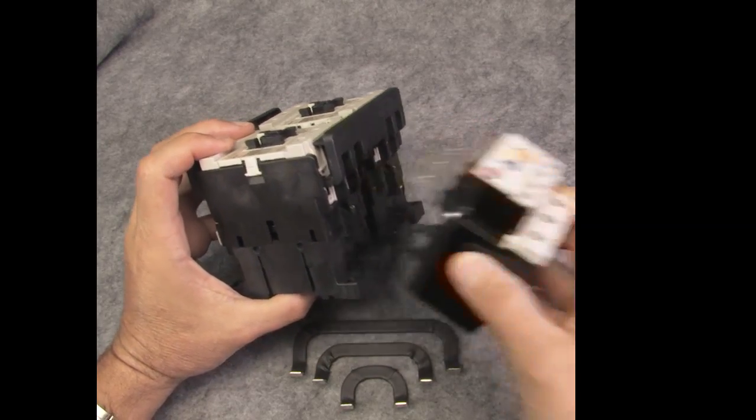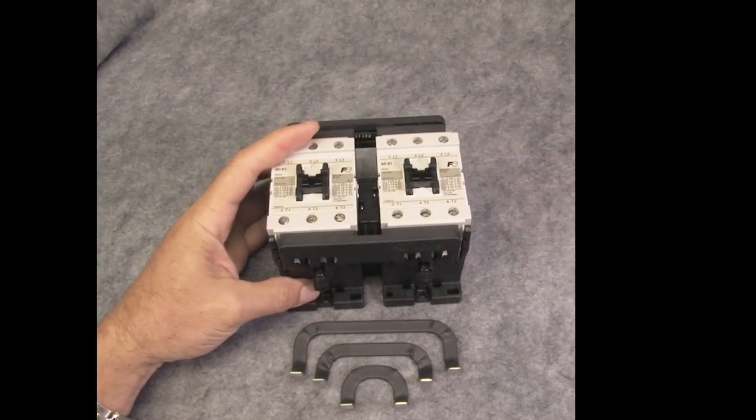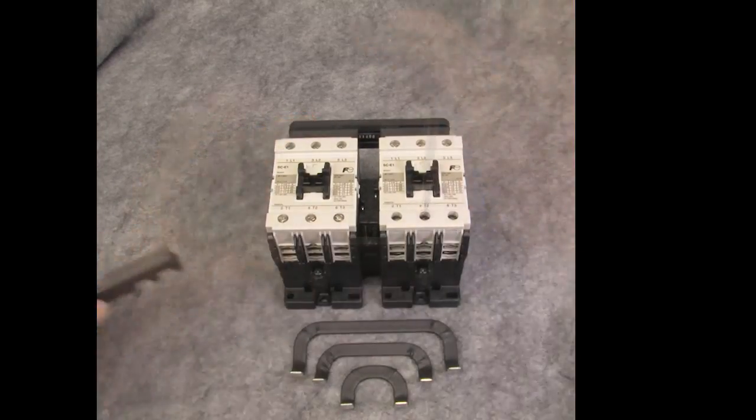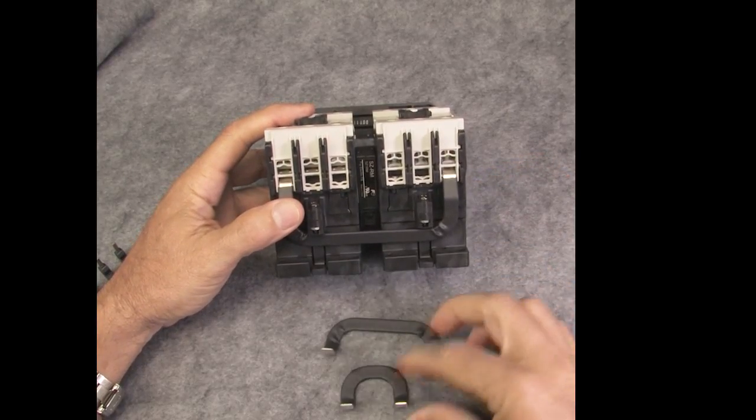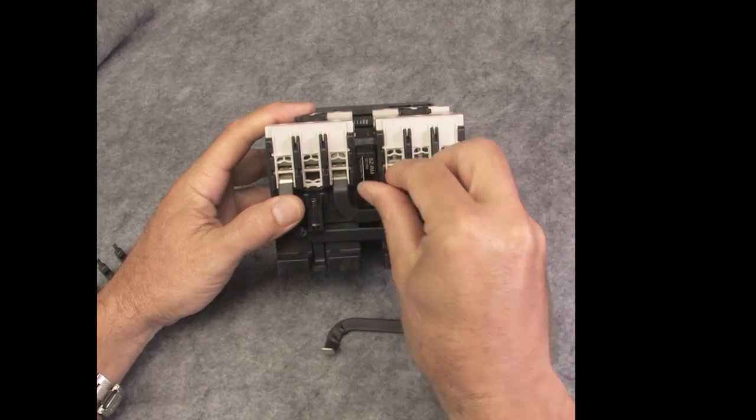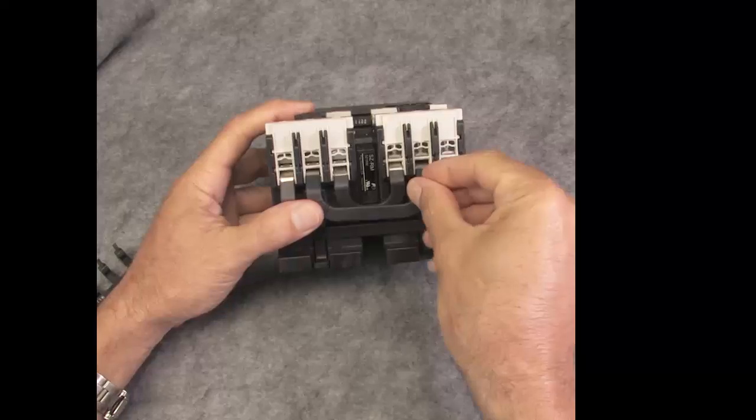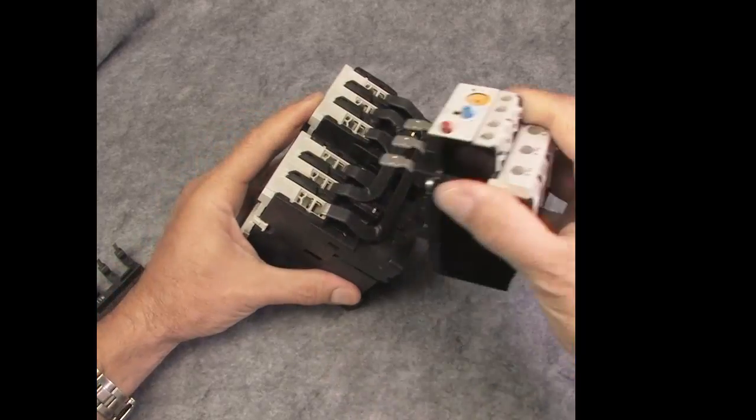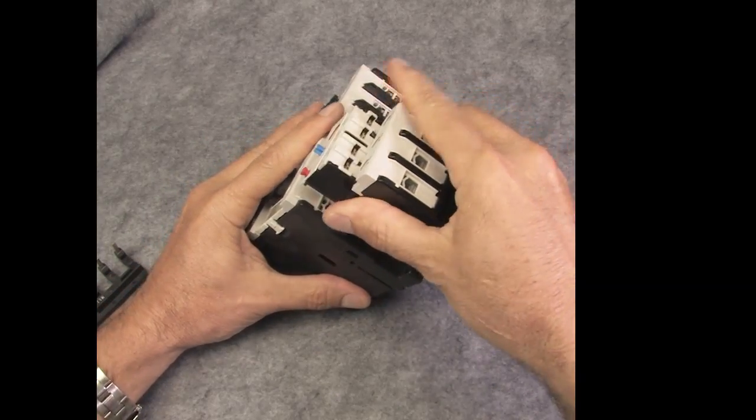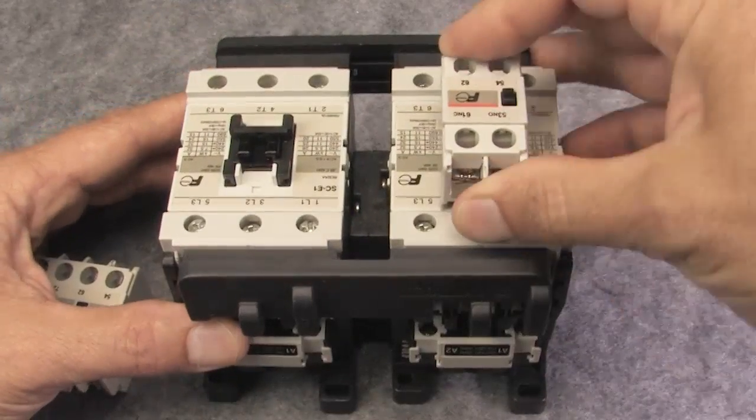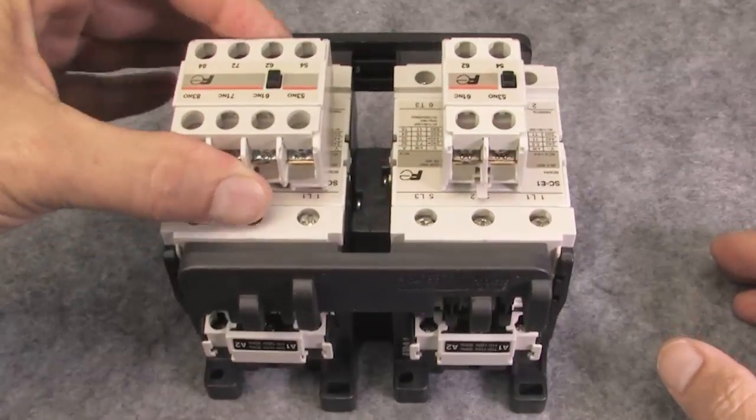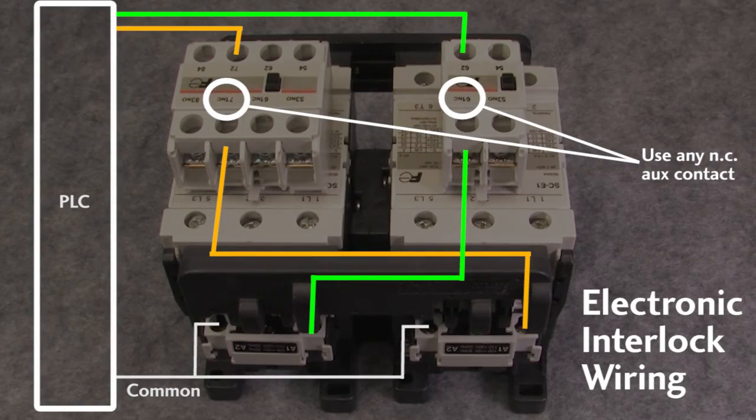For example, I can't add an overload here because the reversing module gets in the way. So if you are planning to use an overload, you'll need a kit like this one for the load side. The parts are flatter so they don't get in the way of the overload. Notice how the middle one sits above the other two and that these mount in the lower holes so the overload can mount in the upper slots. Of course you'll have to add the aux contacts and extra wiring yourself to implement the electronic interlock with this type of contactor.